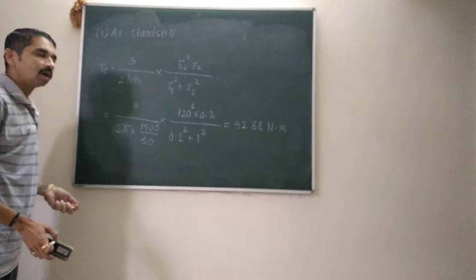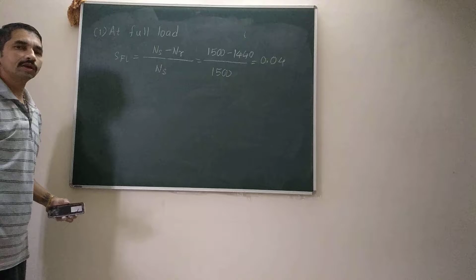So now we have to calculate the 3 parameters at full load. To obtain the values at full load, first of all I have to determine the slip at full load. The value of slip at full load is given as Ns minus Nr upon Ns. If I substitute the values, it will be 1500 minus 1440 upon 1500. The value of slip that I am getting is 0.04 or 4%. Okay, so this first value we have calculated.